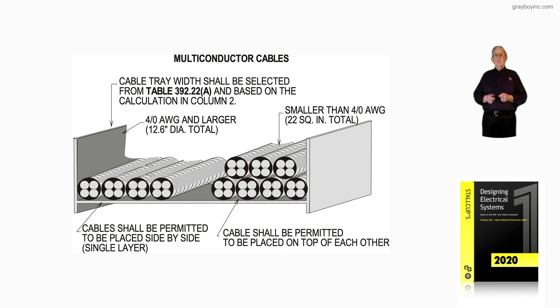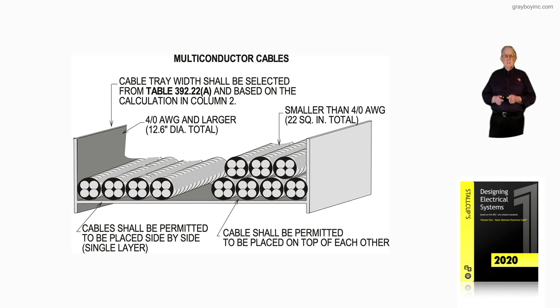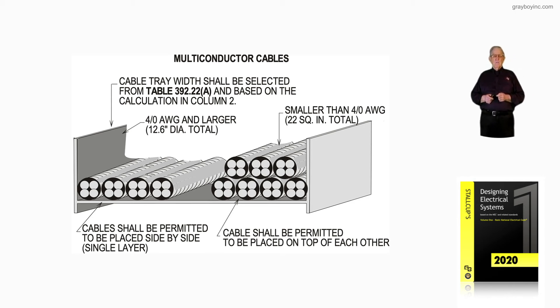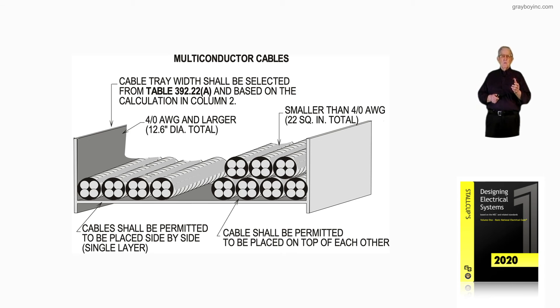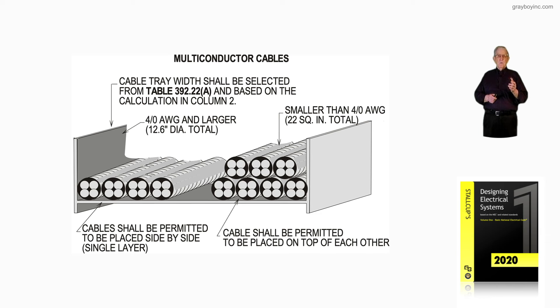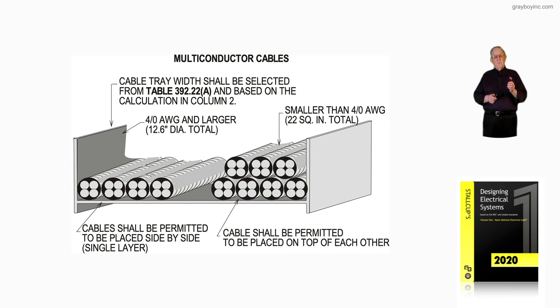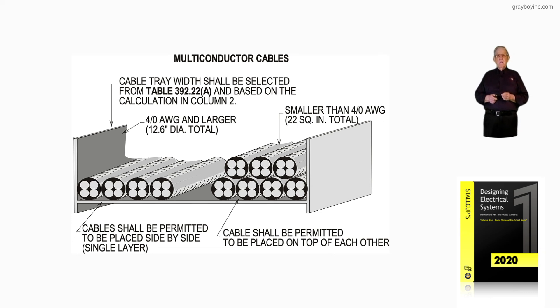To the right, you have smaller than 4/0 AWG conductors, and notice that they're permitted to be placed on top of each other. The conductors to the left — 4/0 AWG and larger — cannot be stacked up on top of each other, because of the damage that might occur if you just keep stacking them up.